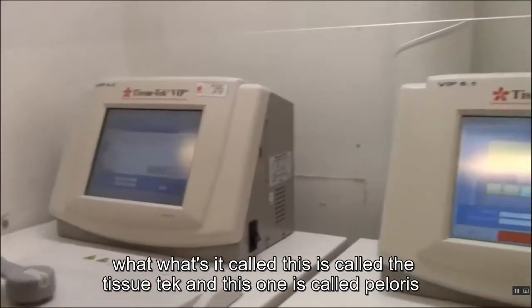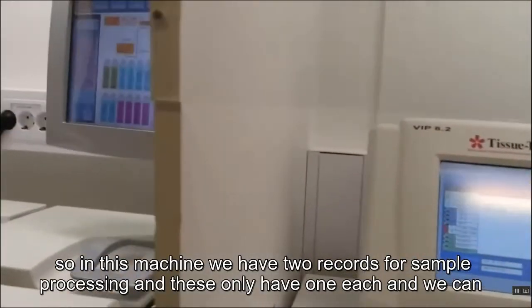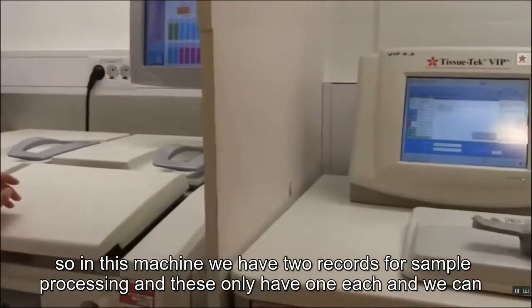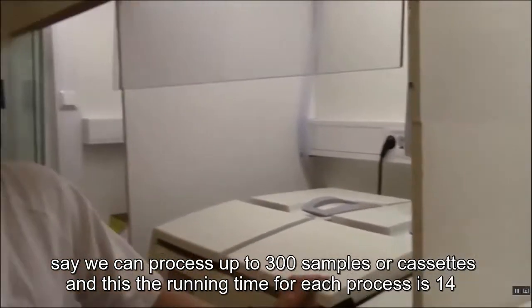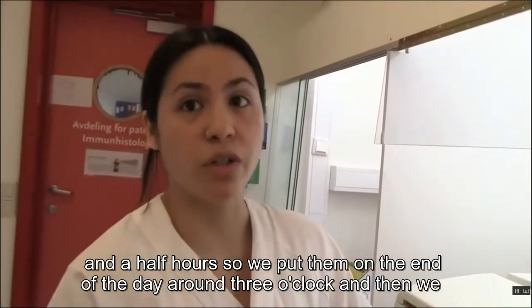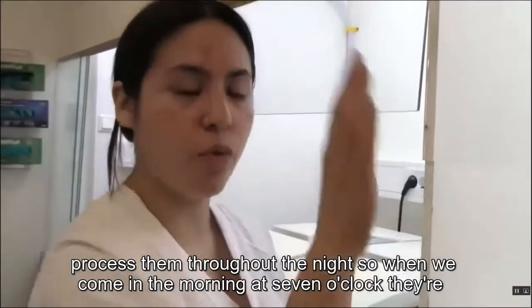These are the machines we use for processing. This one is called the Tissue-Tek VIP, and this one is called Peloris. In the VIP we have two retorts for sample processing, and these only have one each. We can process up to 300 cassettes, and the running time is 14 and a half hours. We put them on at around 3 o'clock and process them overnight, so when we come in at 7 in the morning they're all done.